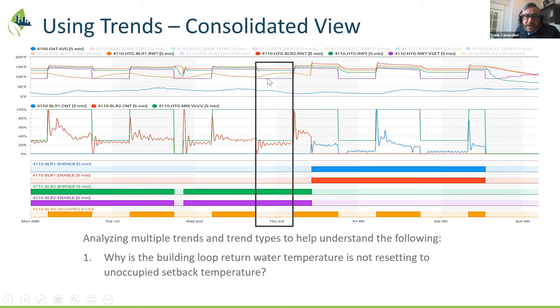If you remember in the first slide, what we were having a problem with was the valve. The temperatures, the set points being set back, this purple line, but the actual temperature in the loop wasn't going back. By having all of this information on one view, which is becoming more and more commonplace in fault detection and diagnostic tools, as well as some BAS manufacturers, we're trying to understand why that's actually happening.